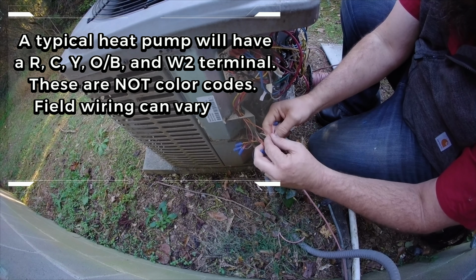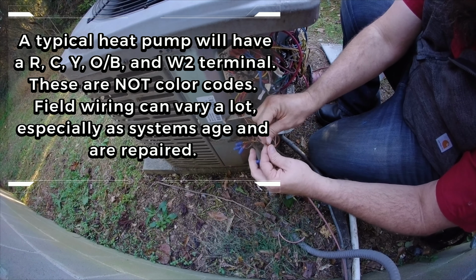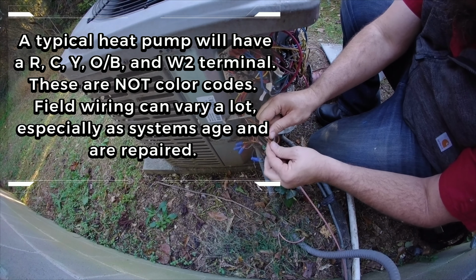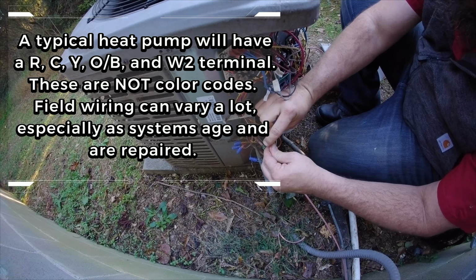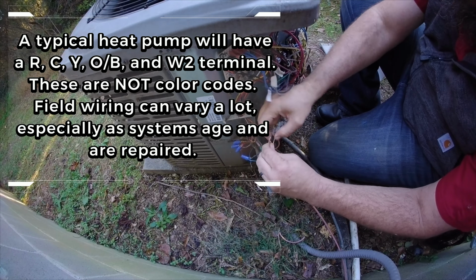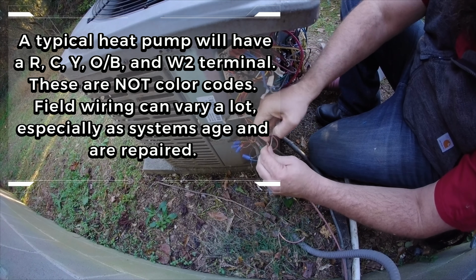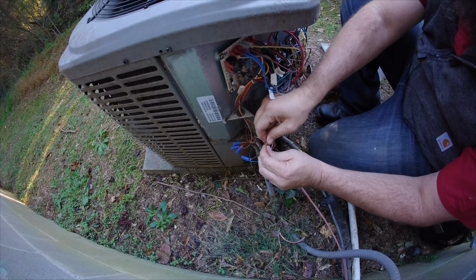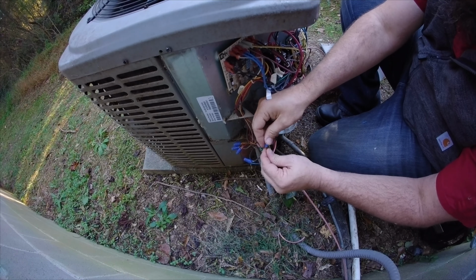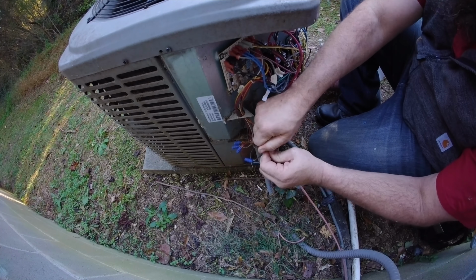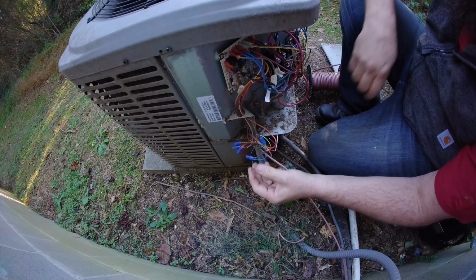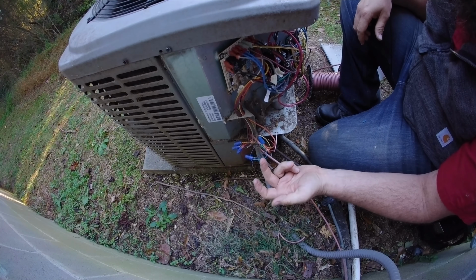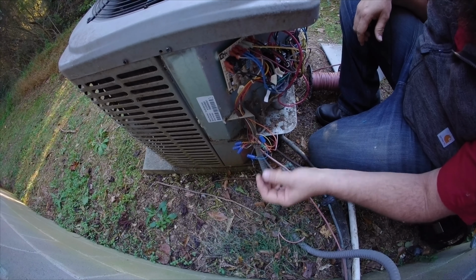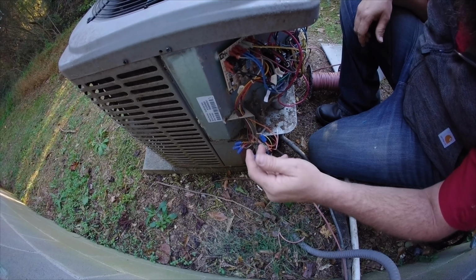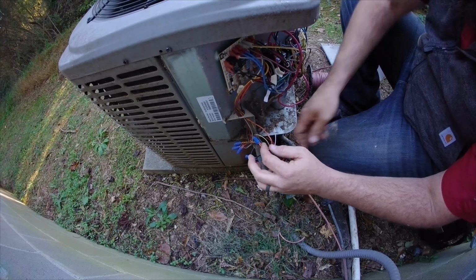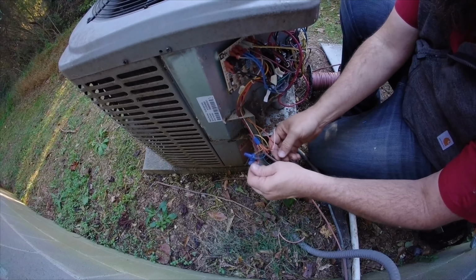Remember, all of these colors are somewhat interchangeable depending on who installs it, so do pay attention to what things are hooked up to if you need to. In other words, there's no real wiring code as far as these go. Most people hook the same color to the same color, but with that in mind, you might end up with blue as a common, black as a common, brown as a common, or blue, black, brown for an O or B, so who knows. Do pay attention to that in the field.